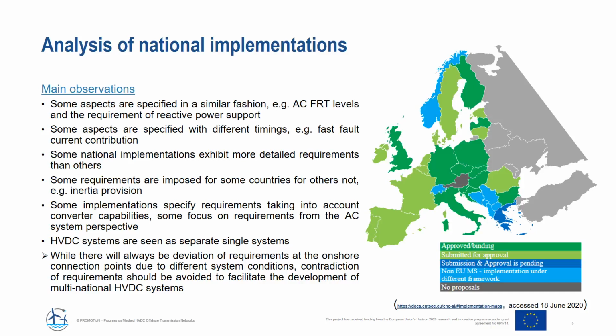So the first observation is that some aspects are specified in a very similar fashion in all the analyzed grid codes. One example would be the AC fault ride through levels and the requirement of reactive power support during AC faults. Some of the aspects specified are then associated with different timings.